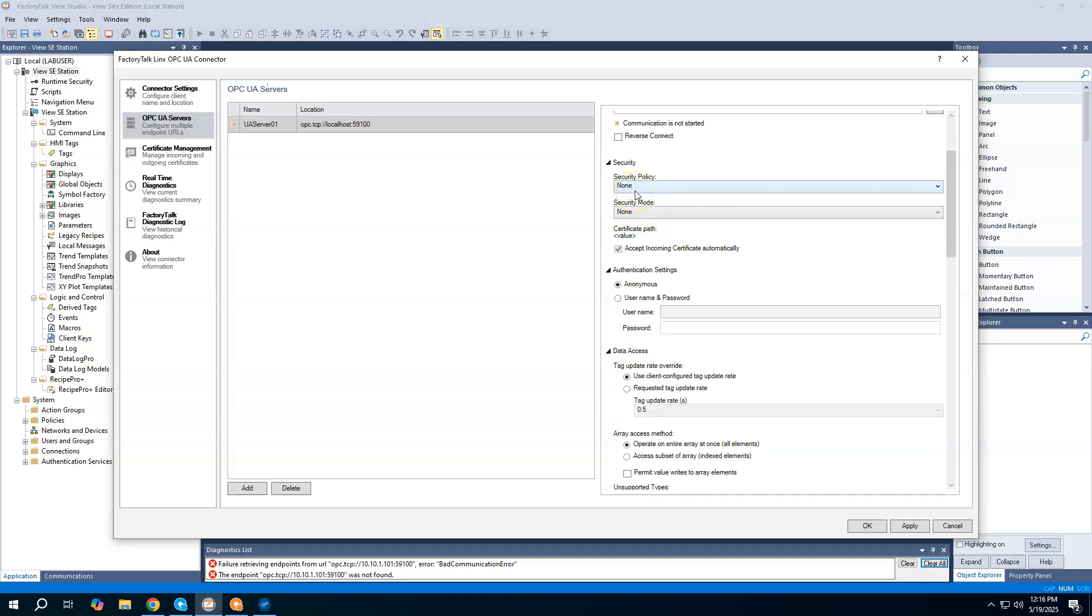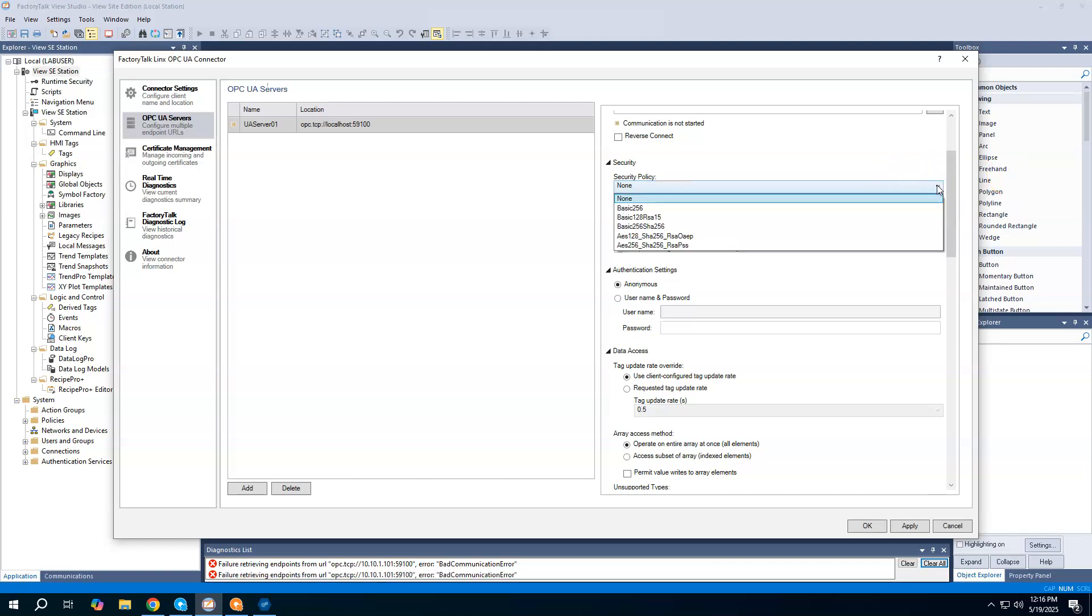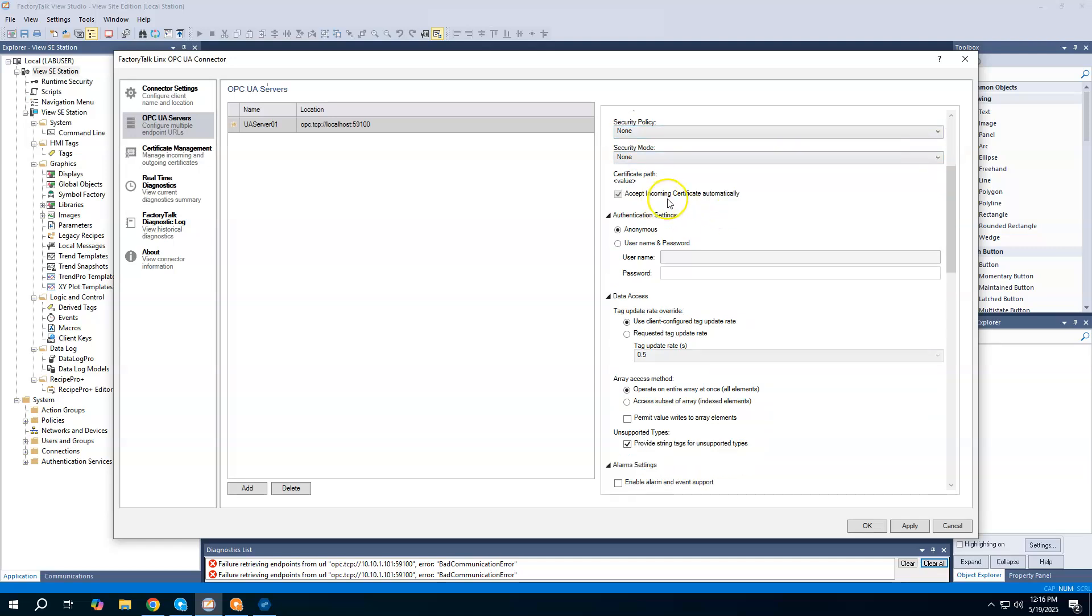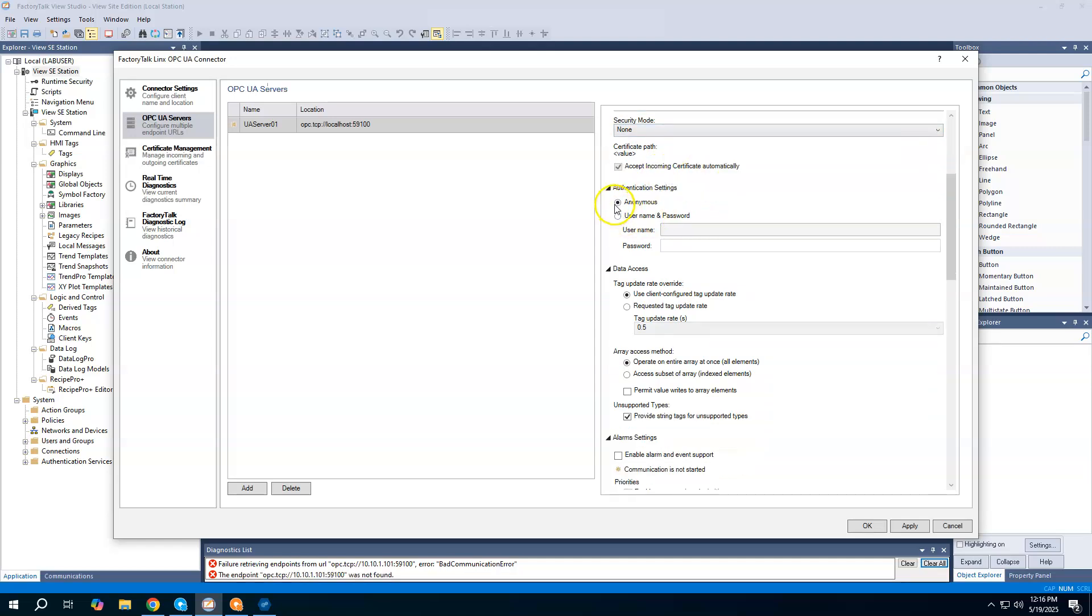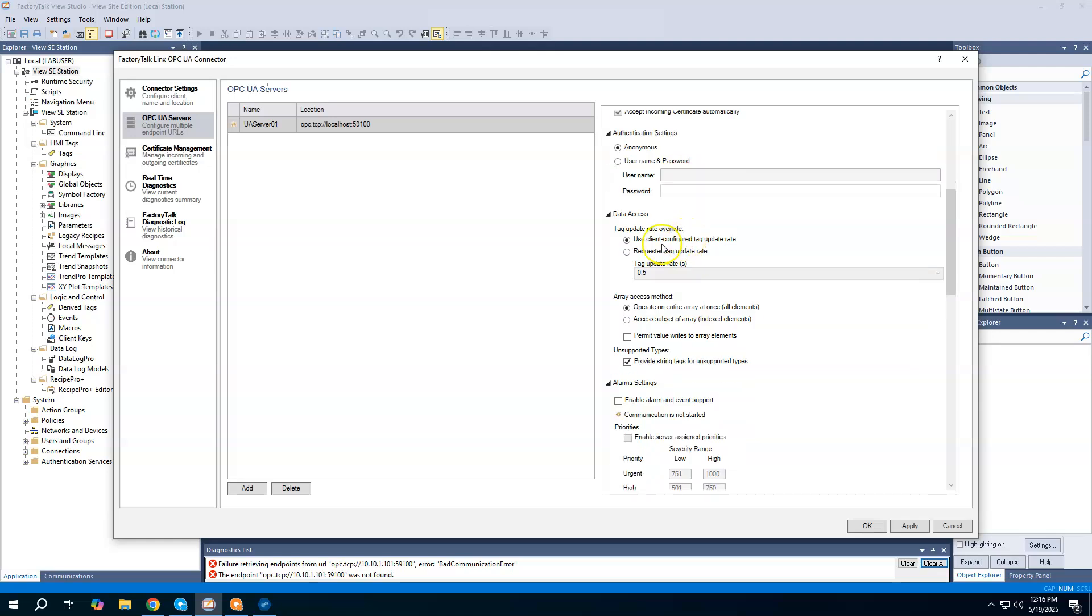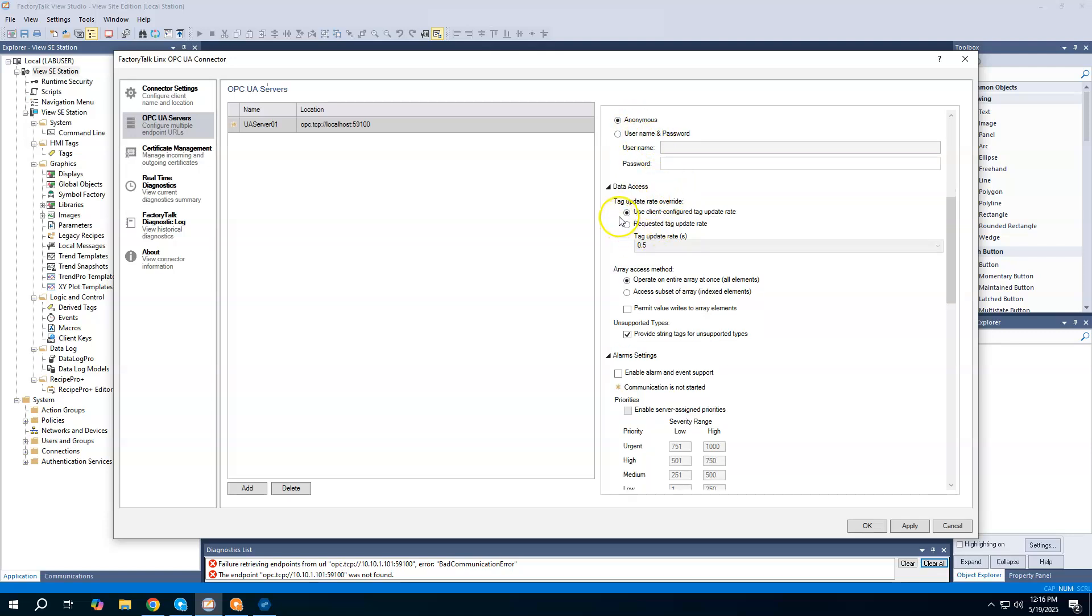I'm not using security for anything here, but you do have the ability to add all the different security levels, encryption methods. I'm going to use the anonymous user, but you could create a username and password to require you to get connected into the OPC UA server. That would have been back there in Optix where we would have defined the username and password. The data update rate we can use either we get to define our own or just use what's coming from the server.